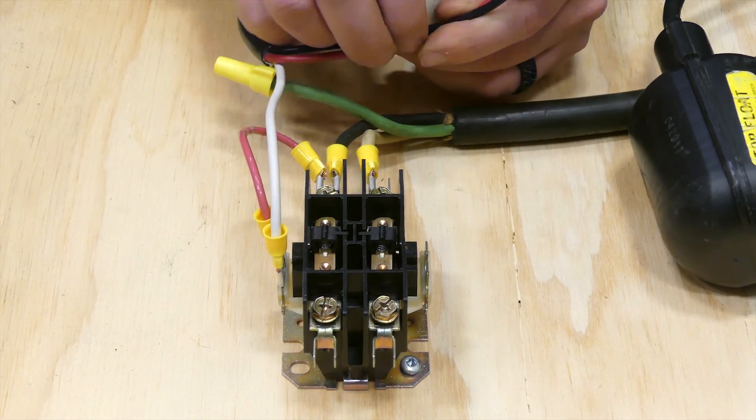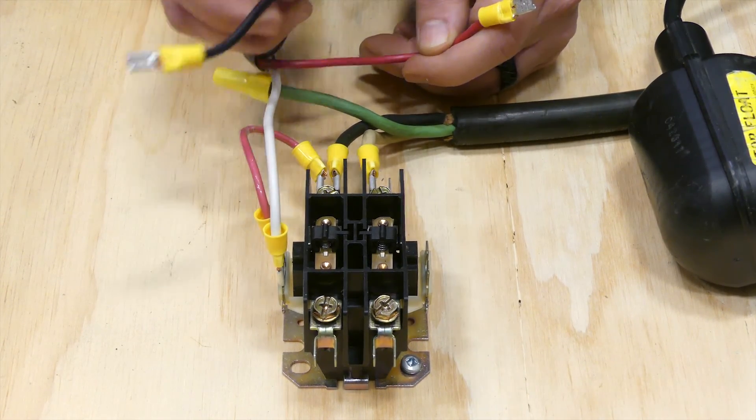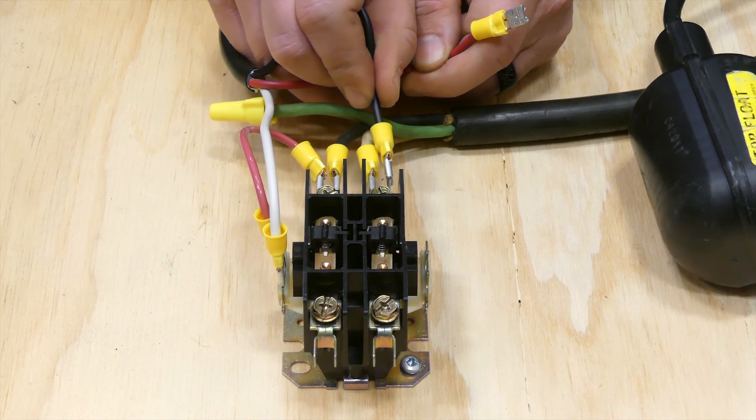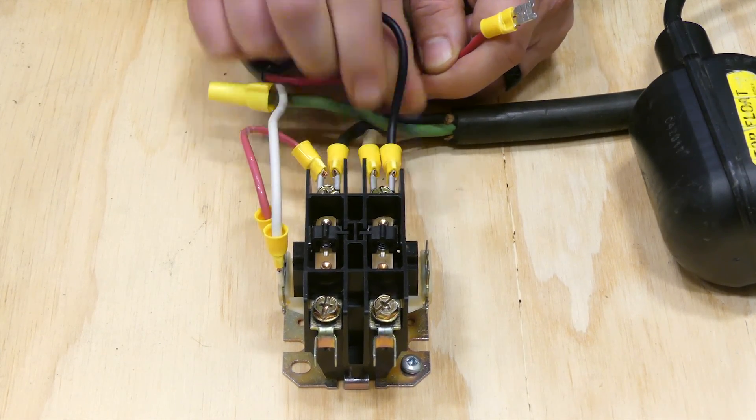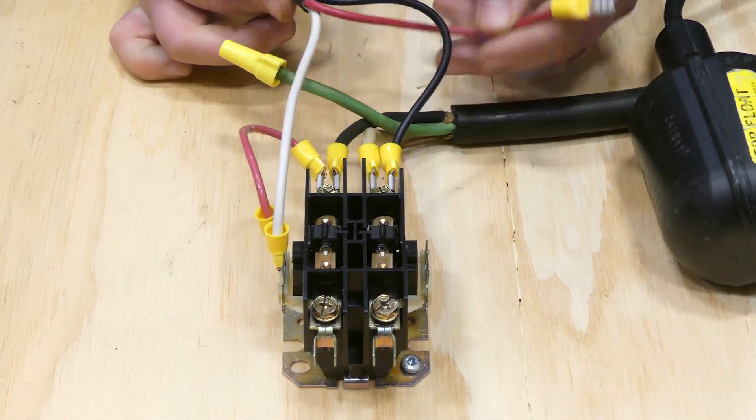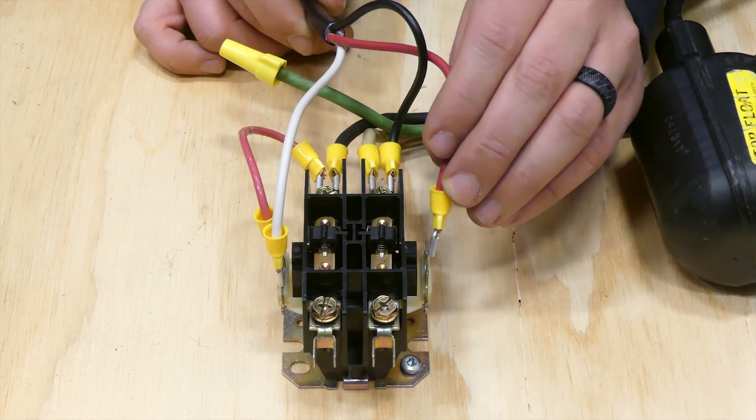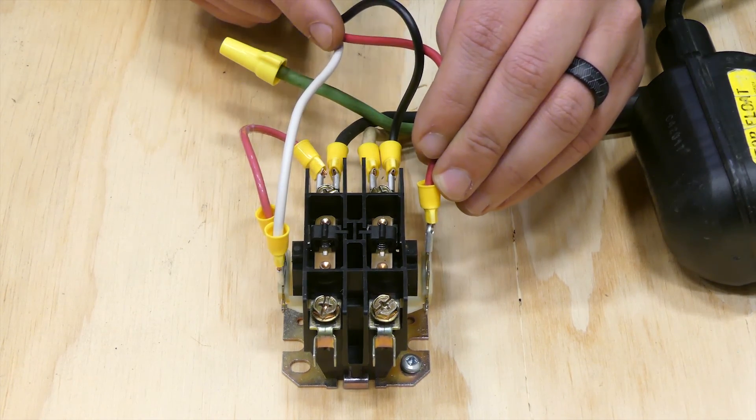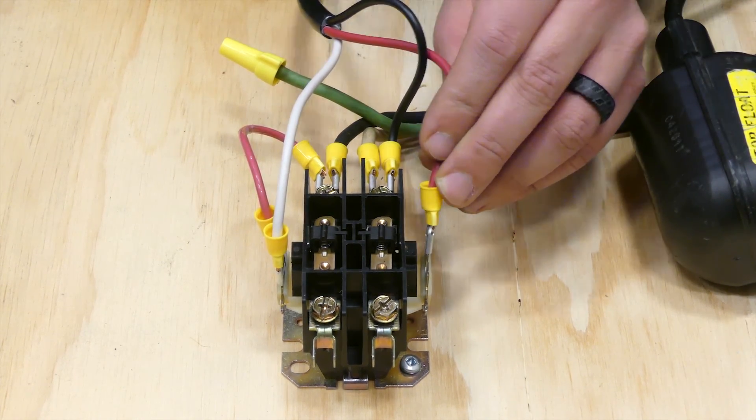We also need to make sure that the black wire is on another spot that is always energized, so right there to share with the incoming power of the system. That leaves the red wire to lead to essentially jumper that power through the black wire, through the float switches, and back to the coil to complete our 220 volt coil circuit.